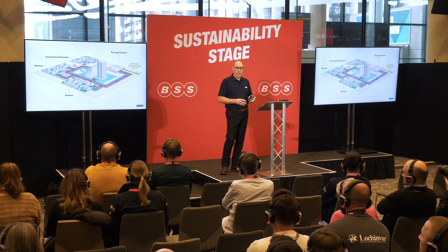So with that in mind, you'll have several sites within that network. This particular one is a school up in Glasgow, and this was done back in 2013-14. The engineer at the time wanted to know how he could reduce his carbon emissions off his site, and what he ended up doing was employing a ground source heat pump. In actual fact, they sunk the boreholes, which are this flow and return piping system, and connected to that were 5 CHPs.